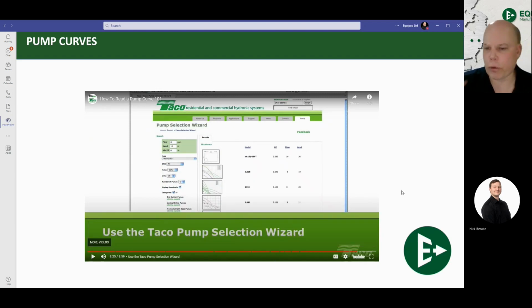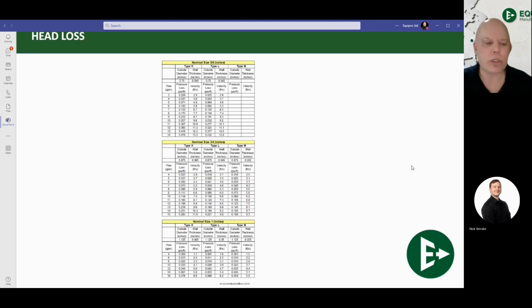So yeah, we're going to stop the video there. Long and the short of it is, I just want to give you an overview of what a pump curve even is. What do these things even look like, and how do you use them? Again, it all goes back to the heat loss. Heat loss tells me how many BTUs I need to put in an area. Once you know the BTUs, I can calculate how many GPMs I need to put that amount of heat in the area. And then I get into the final part of it, which is calculating the head loss through my heat emitter. Heat emitters, again, are your radiators, your air handlers, and your radiant in-floor. Those are all going to have their own charts with regards to head loss, which I'm going to show you here in just a moment. But there's also the pipe in between that has its own pressure loss.